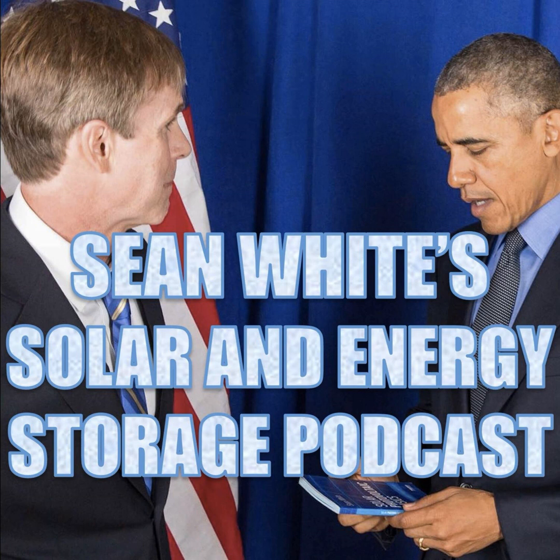So it's possible that somebody could have a huge load that's bigger than what their solar inverter can handle, but it only works when the generator is turned on. A lot of people that are living off grid, they know that they can't vacuum and have the refrigerator running at the same time. They need a bigger inverter. Yeah, they need a bigger inverter. But they're not required to. That's the important thing, that if you want to live that way, have at it. And again, these are standalone systems.